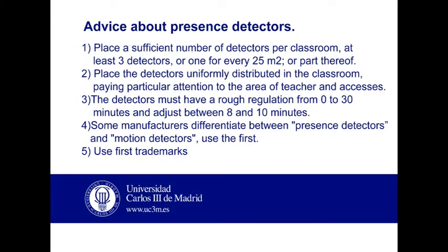Follow these suggestions to select the presence detectors. Advice 1: Place a sufficient number of detectors per classroom, at least three detectors, one for every 25 square meters.